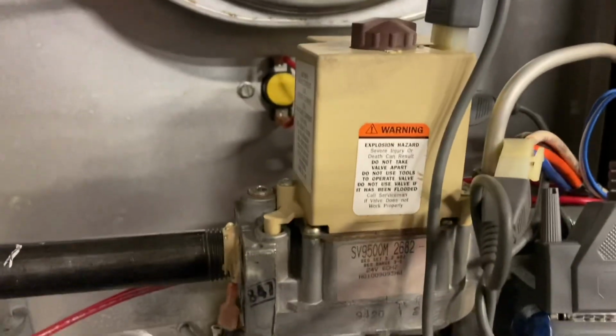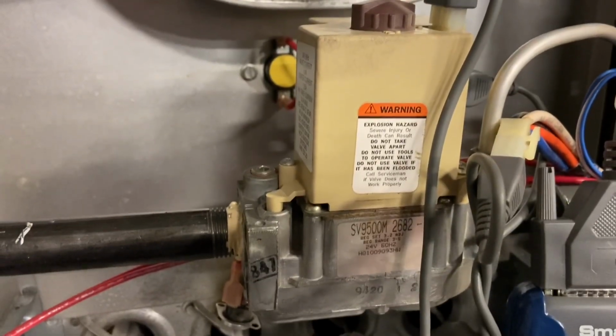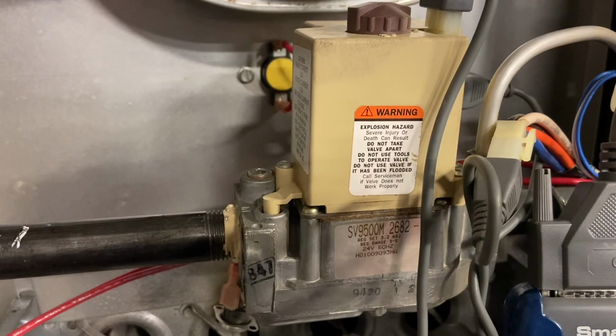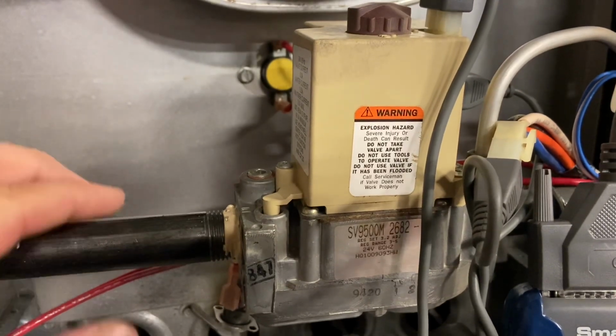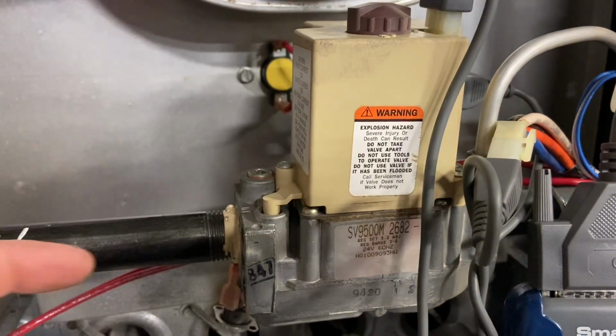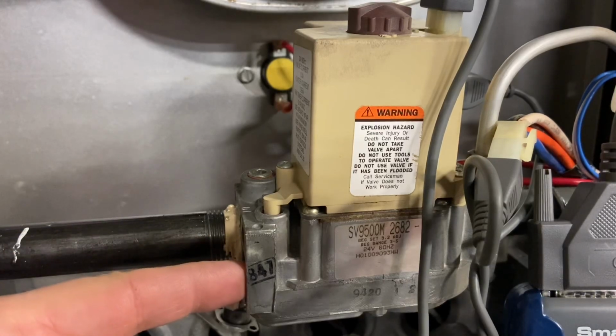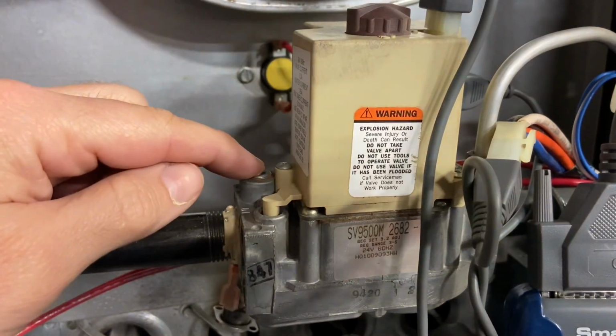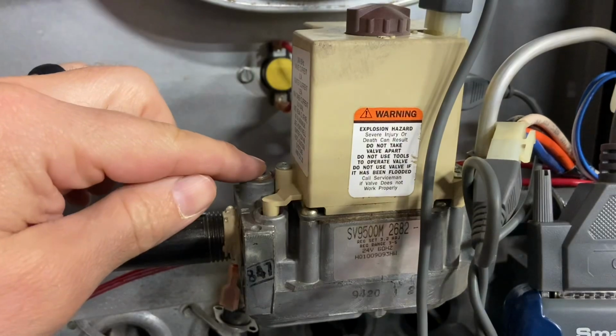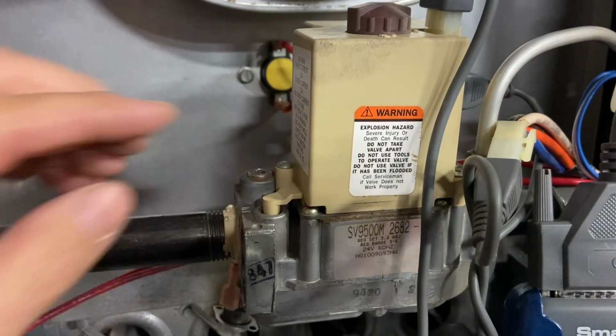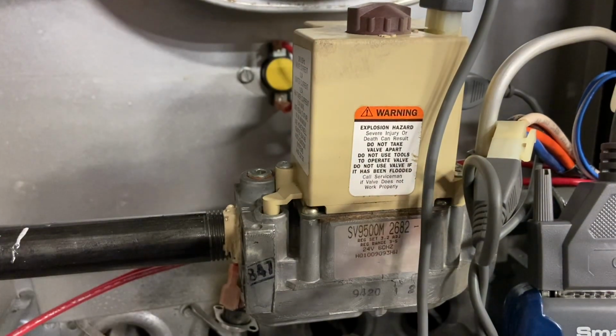So next I want to focus in on this combination gas valve. This is one of the earlier models of the smart valve, but it still works the same way. This port here is also the same side as our inlet gas pressure. So we could actually put a manometer here. We'd shut our gas off. We could put a manometer here to see if we had the correct gas pressure coming into this system.